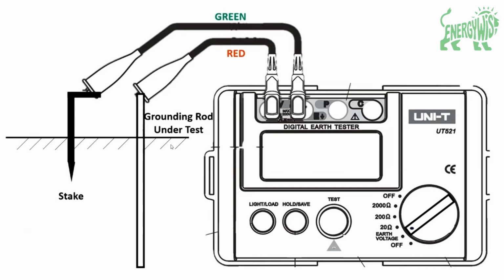Now, to measure, the first thing we have to do is check the voltage. To check the voltage, we connect the red lead to the ground, and then we connect the green lead to the earth spike. When we put the probe to the earth voltage terminal, if we measure a voltage between 0 and 10 volts, that means there is a connection between the ground and the system cable. But if it's greater than 10 volts, we have to check the connection with the ground rod, reconnect it, and check again. If it is between 0 and 10, it's okay, so we can proceed.